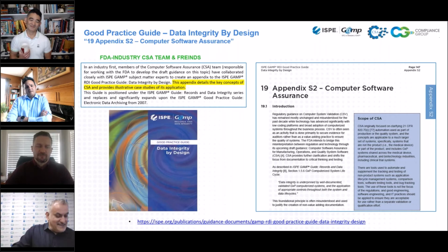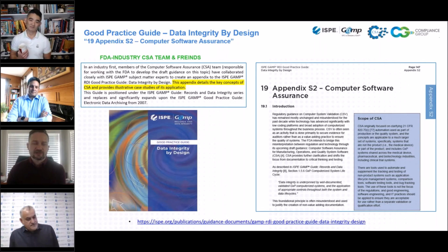No, you don't need to. So I always recommend for your higher risks, and if you're going to CSA 4 or 5 and a traditional FMEA, the high risk, that you look at mitigation strategies on those and that you verify those mitigation strategies work during your validation. Your low and your medium risk, no, it's not necessarily to mitigate them. It's to be aware of them.